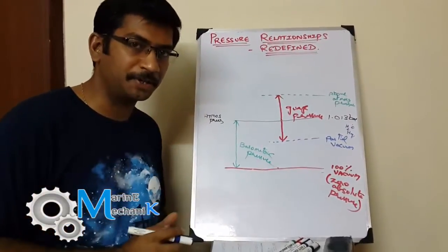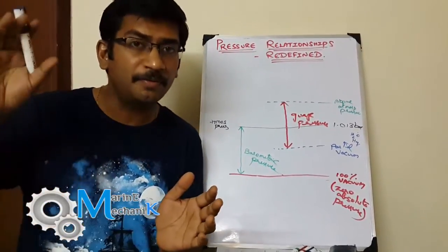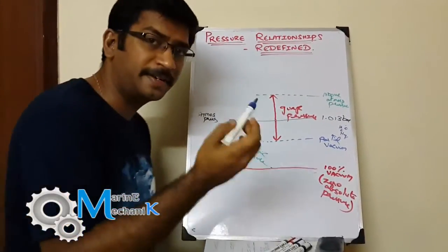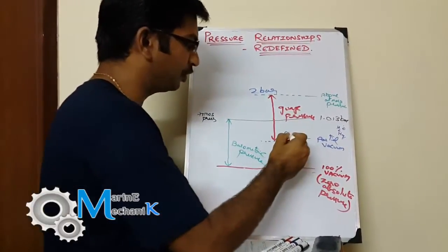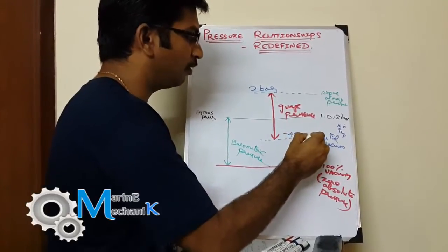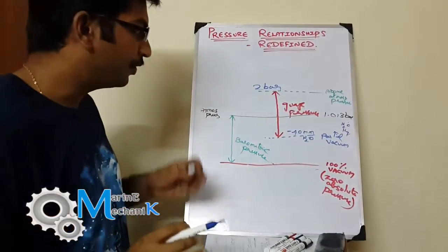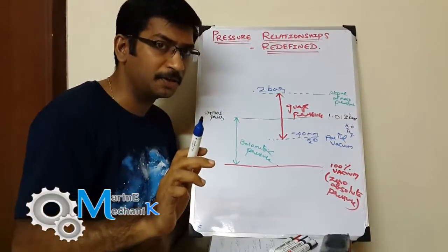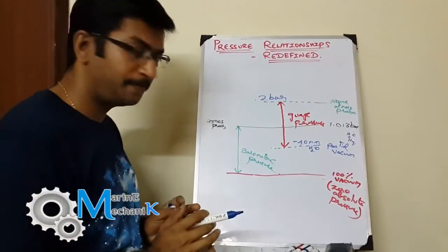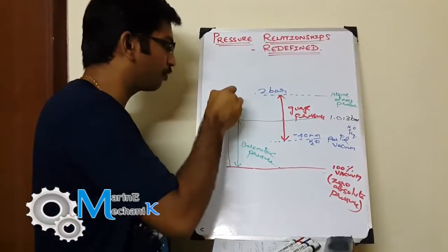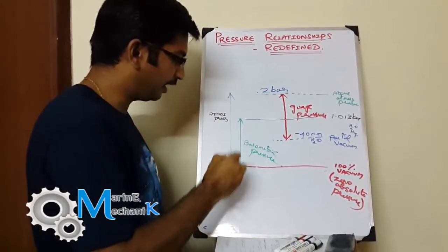The last concept is absolute pressure. Zero absolute pressure is completely different from absolute pressure. If the gauge reads a pressure above atmospheric — say 2 bar, which is roughly 1 bar above atmospheric — then absolute pressure equals gauge pressure plus atmospheric pressure. You measure from the gauge reading all the way down to the zero absolute pressure line. That total is the absolute pressure.